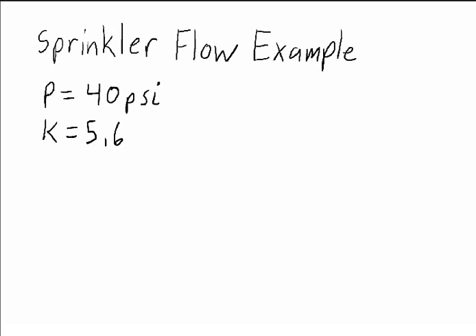Hello everyone. This video is going to give an example for how to calculate the flow coming out of a sprinkler given a known pressure and a k-factor. So let's say we have a pressure at the sprinkler head of 40 psi and a sprinkler with a k-factor of 5.6.